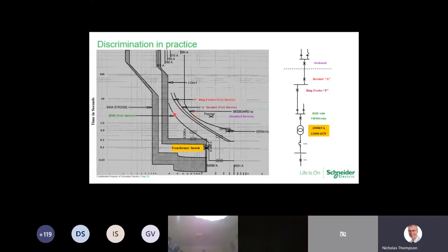Now we're moving down to our ring main unit circuit breaker curve in the protection relay. Here we're using a very inverse curve, and this is a VIP 300 relay. We can see we're using a two set point setting: the first set point here, and then the second set point here with a definite time curve. We can see how it follows and then drops down, mirroring the LV. Now there is a slight problem here where we've got the LV crossing over the HV. This would have to be taken into account when doing this study.